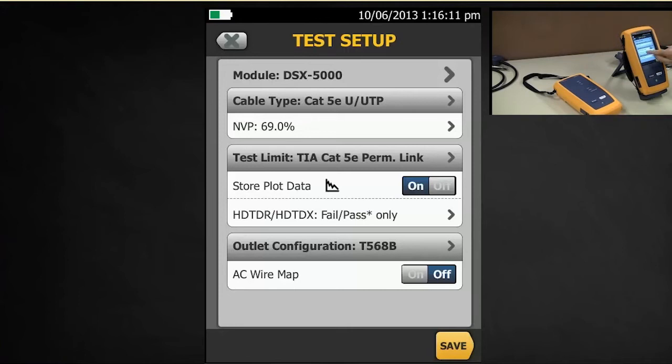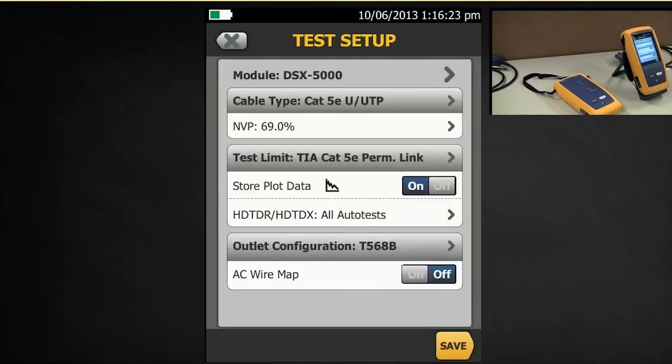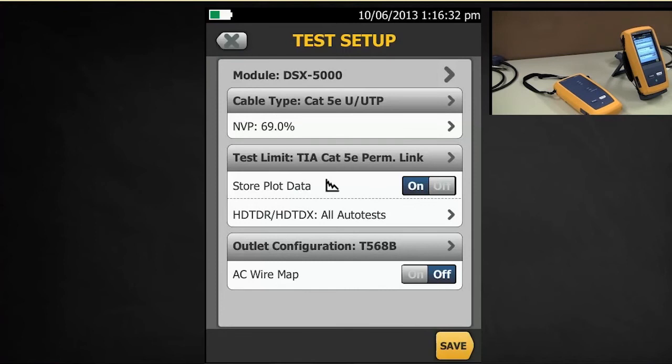If you tapped on the HDTDR, HDTDX, you get two options here. You can have it run when it only fails or is marginal pass, or you can have it run at all auto tests. Now, if you do run it with all auto tests, that means the HDTDR and the HDTDX is going to run every time regardless of whether it passes or fails, and it's going to add about three seconds to the test.